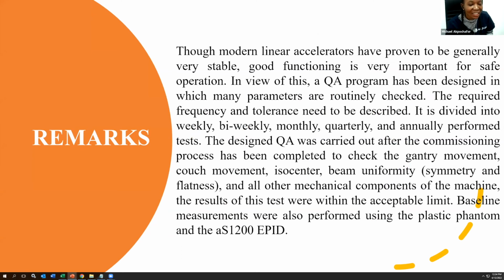But one thing that is common, I think, is that because the machine has beamed during the period of acceptance testing, everybody feels, oh, this machine can now start working, let us start treating patients. There will be a lot of pressure on medical physicists. In fact, here there was a lot of pressure, like, the machine can start treating because it has beamed. But as a medical physicist, you say no, until this is done, we cannot release the machine for clinical use. During this phase they keep asking, physicists, is the machine ready now to be used? But you have to be very careful because nothing must go wrong with the commissioning. If anything goes wrong with the commissioning, it affects the overall quality of the treatment. So it is very, very important.